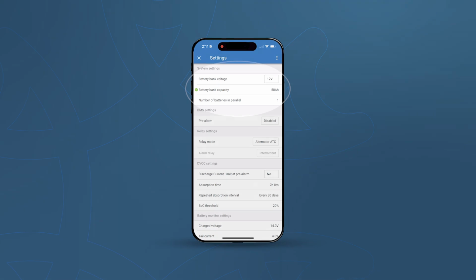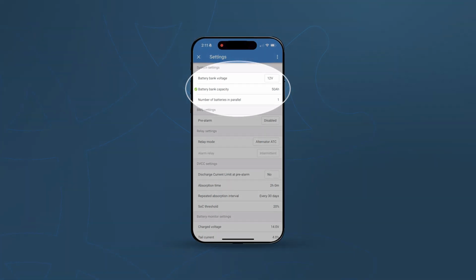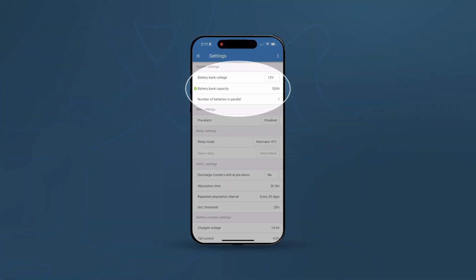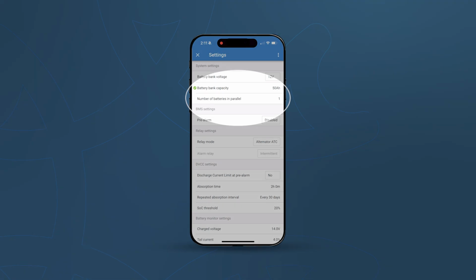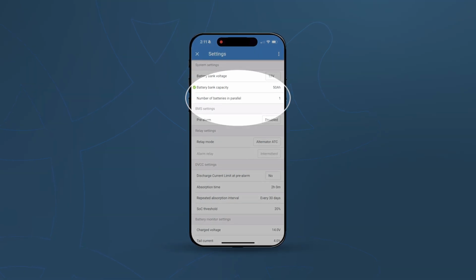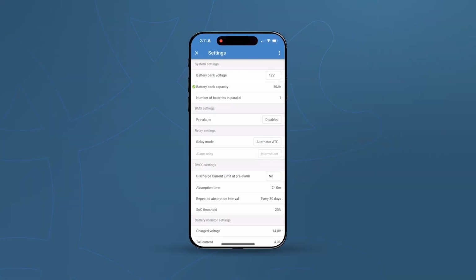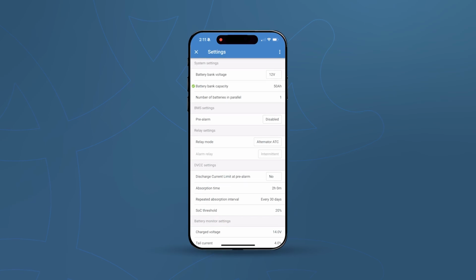I'm then going to change the battery bank capacity, which in our case, we have a 50 amp hour battery bank. It's then going to ask me the number of batteries that are in parallel. In our case, we only have a single battery. If you had 2, 3, 4 batteries here, this is where you would change that. When you go to a 48 volt system, it's important to remember that each series battery counts as one. So if you have two 24 volt 200 amp hour batteries ran in series, that's one battery in parallel.